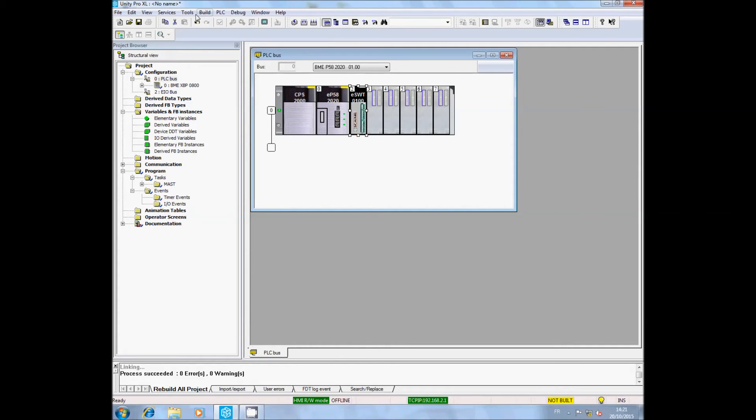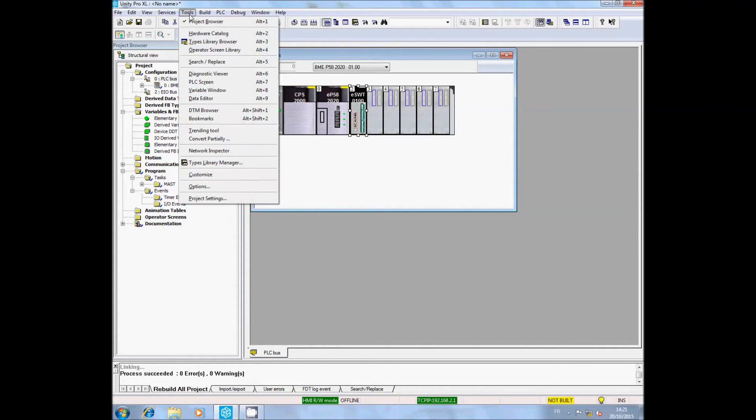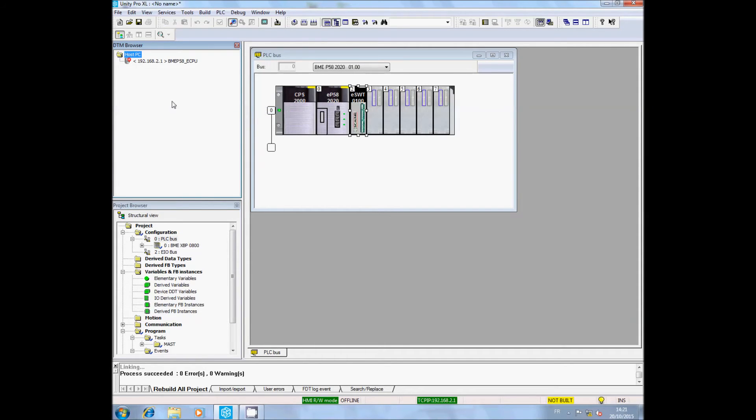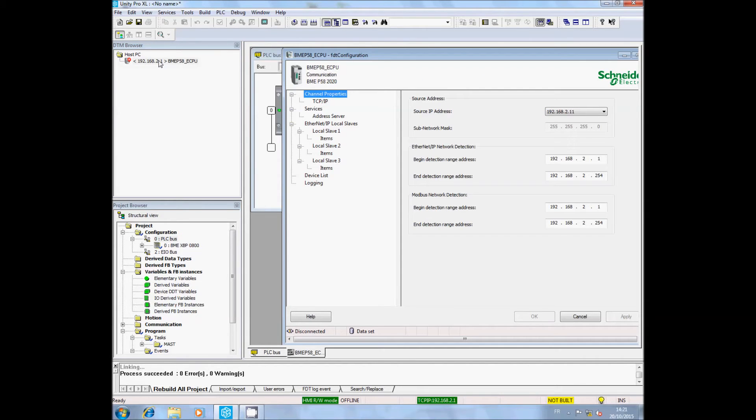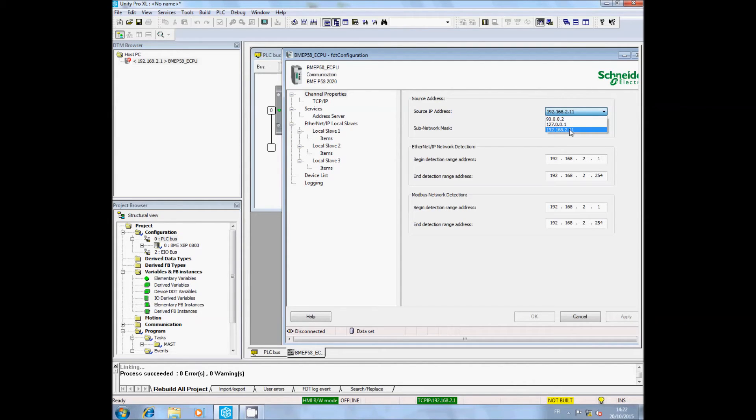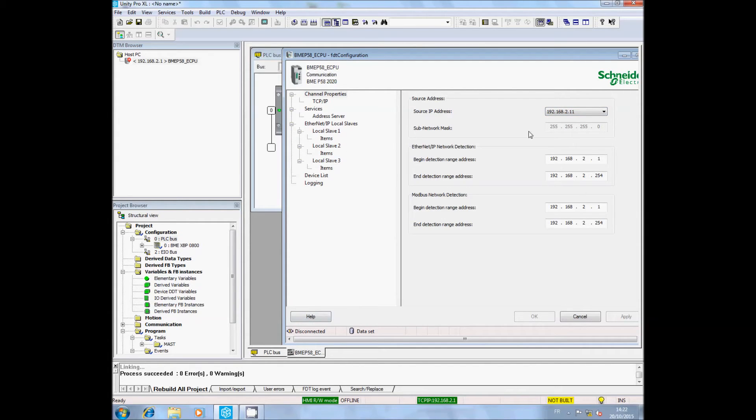In Tools, select the DTM browser. Double-click on the M580 DTM. The CPU configuration appears. In the source IP address, select the IP address of your PC if you are working via Ethernet, or choose the USB address if you are using the USB cable. This is very important to communicate with the PME.